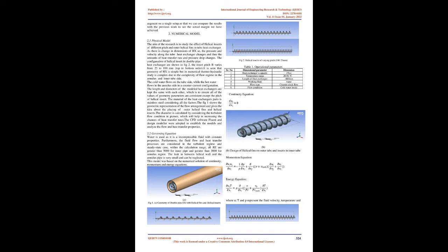In 2013, Nanan et al. [5] studied the co and counter helical twisted tapes in a tube HX where twist ratio was 3 to 5 and angle was 30 to 90. It was found that at constant conditions, counter swirl does better than co-swirl. Counter swirl consistently leads to significantly higher friction factor than co-swirl, as counter swirl generates higher flow hindrance. The TPF obtained by co-swirl insert is slightly better than that given by counter swirl insert, up to 4.7%.